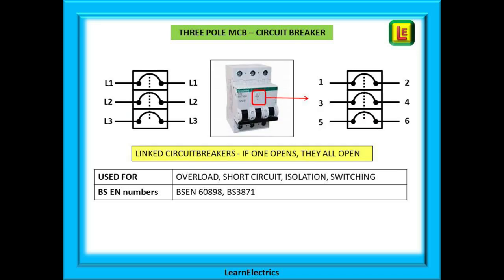MCBs are available as three pole devices too — one set of contacts for each of the three phases, linked so all three operate at the same time. We never run a three-phase machine or motor on just two phases as we can damage things by doing this; so if one phase has a problem and disconnects, all three phases disconnect together. As with the single pole variety, they can be used for overload and short circuit protection, functional switching, and can be locked off for safe isolation. The three pole MCB can be labeled L1, L2, L3 or numbered one to two, three to four, and five to six — a common numbering shown on the front of the MCB in industrial installations.